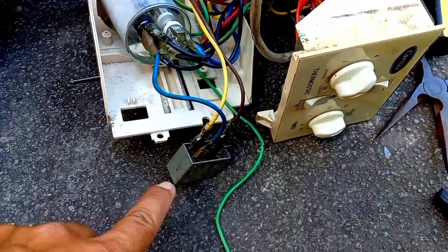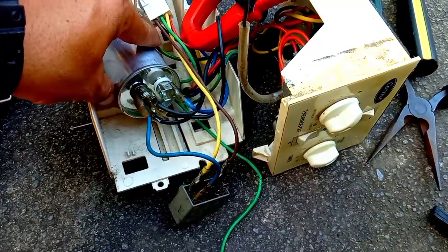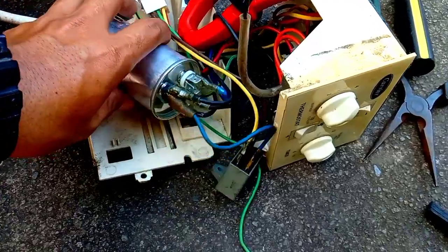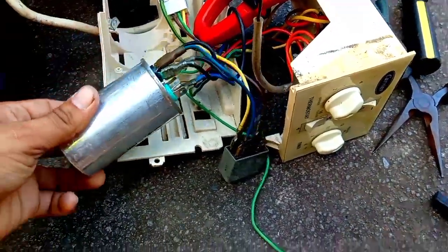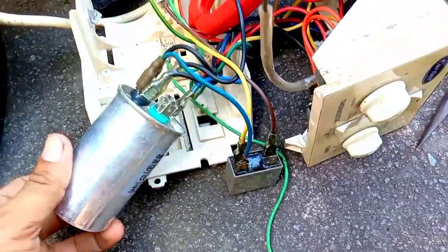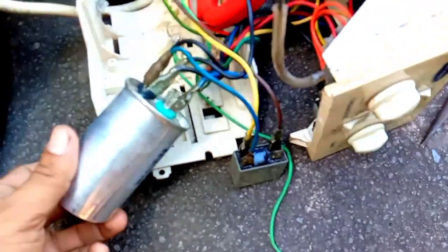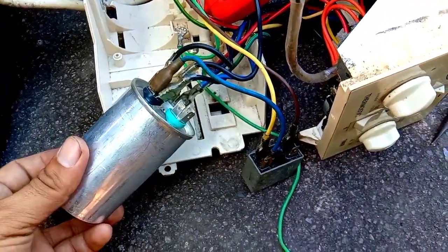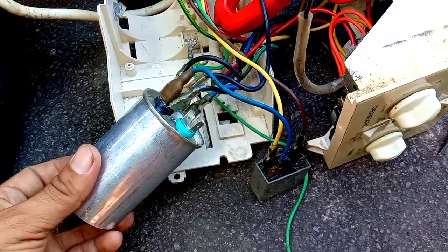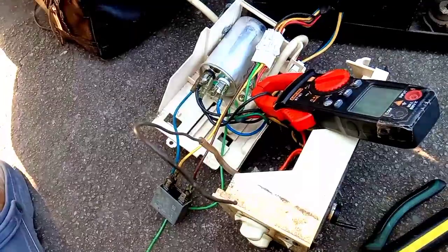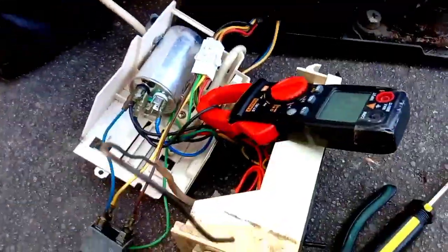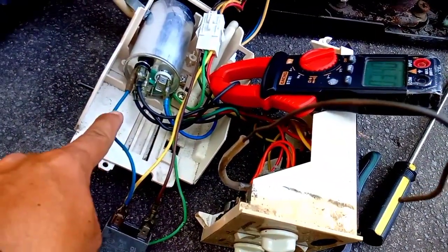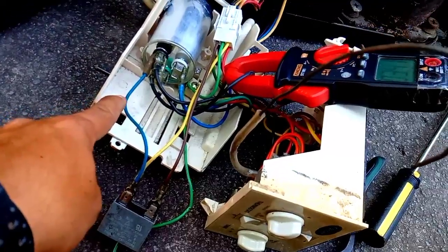Before you install or rewire this unit, especially when it comes to dual type capacitors, we need to change it to single type capacitors. When it comes to single type, only the wire of the compressor is connected to the running capacitor, which is the 25 UF microfarad. And then the fan motor separately has only one fan capacitor, which has a value of 2.5 microfarad.